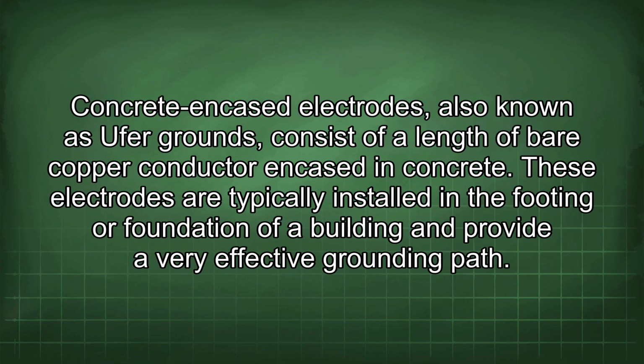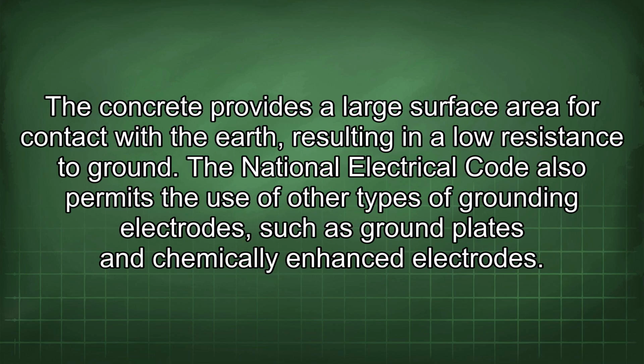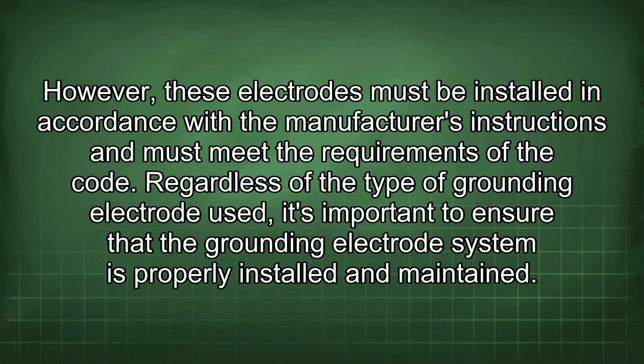Concrete encased electrodes, also known as Ufer grounds, consist of a length of bare copper conductor encased in concrete. These electrodes are typically installed in the footing or foundation of a building and provide a very effective grounding path. The concrete provides a large surface area for contact with the earth, resulting in a low resistance to ground. The National Electrical Code also permits the use of other types of grounding electrodes, such as ground plates and chemically enhanced electrodes. However, these electrodes must be installed in accordance with the manufacturer's instructions and must meet the requirements of the code.